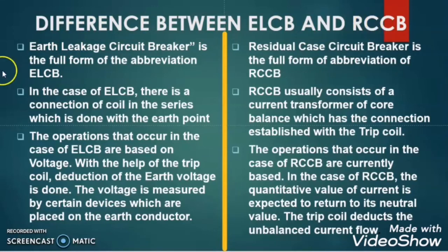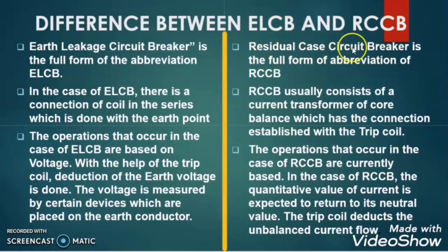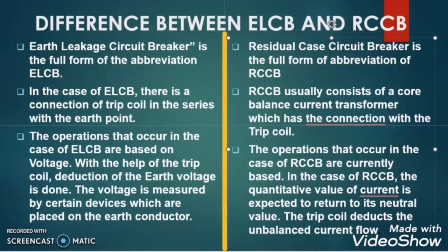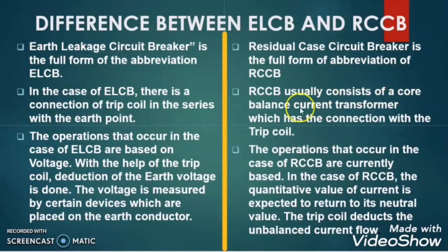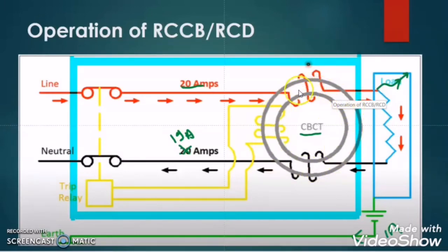The difference between ELCB and RCCB: First, ELCB stands for Earth Leakage Circuit Breaker, while RCCB stands for Residual Current Circuit Breaker. Second, in the ELCB the trip coil is in series with the earth conductor. But in the RCCB there is a core balance current transformer connected with the trip coil and trip relay.